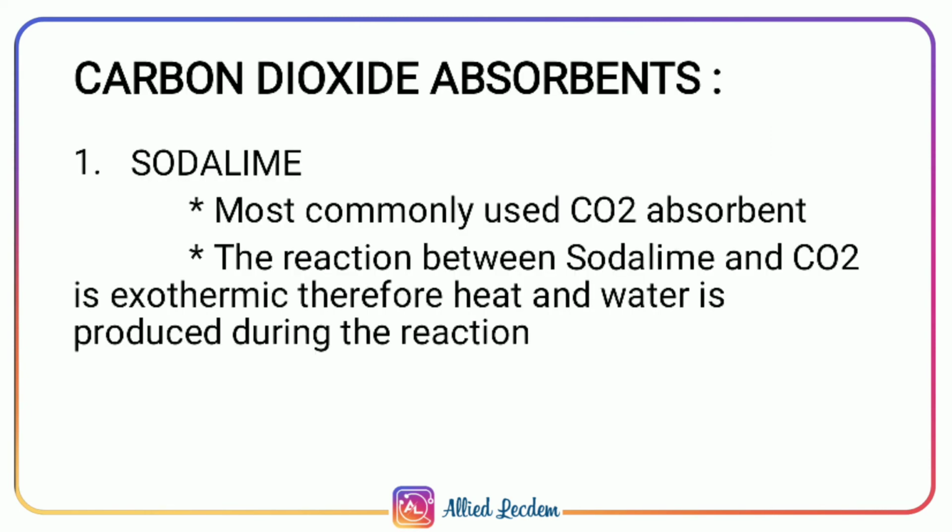Carbon dioxide absorbent, soda lime. Soda lime is the most commonly used CO2 absorbent. They are small granules and it absorbs the CO2 exhaled by the patient. The reaction between soda lime and CO2 is exothermic, so heat and water are produced as a result of their reaction.